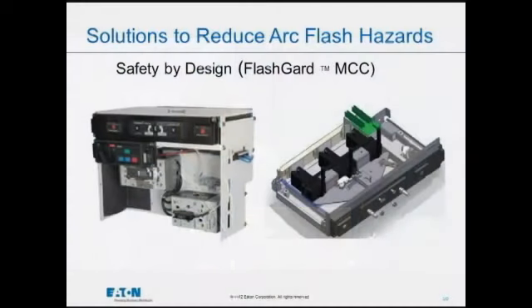Eaton makes product changes. One way to get the arc flash hazard down is to come up with new ideas, like why are we doing it the way we used to do it? And this is one example of a change in design for motor control centers, making it more or less 2 pieces with a crank. And the part on the right-hand side is those contacts are ganged together. They move together. All 3 contacts can move in or out or make connection with the main bars or be pulled away from the main bars with a crank handle. And then it's an option for the operator.